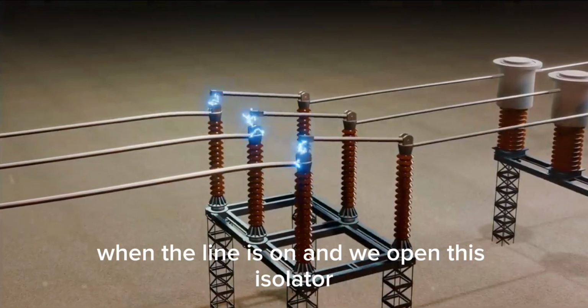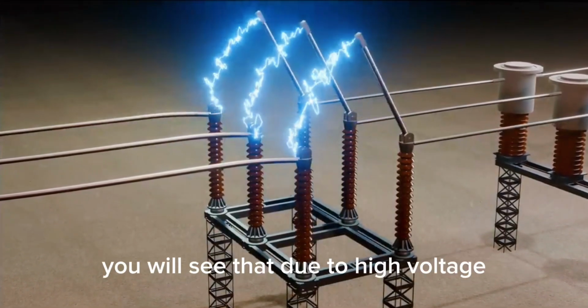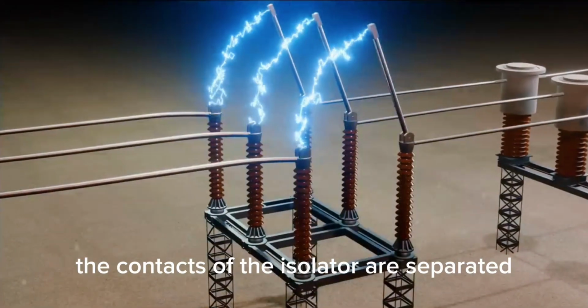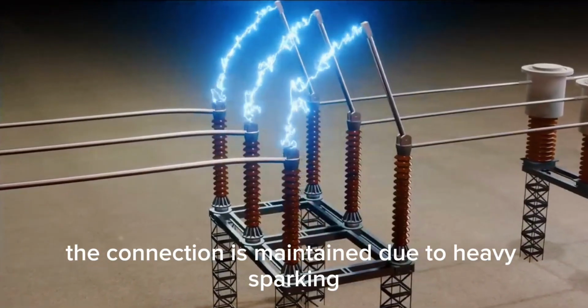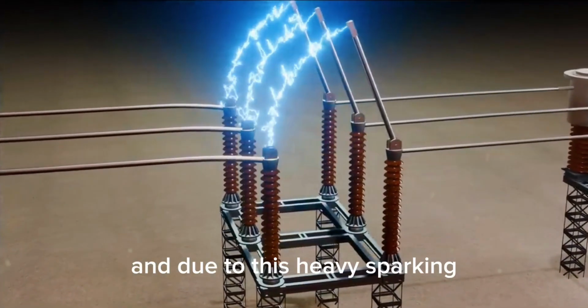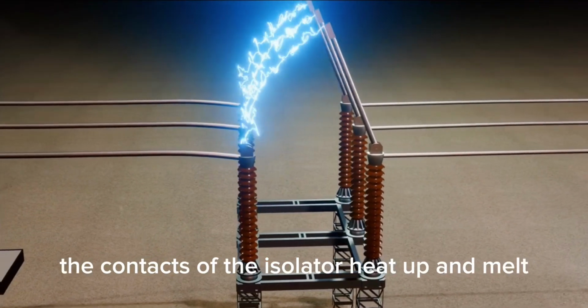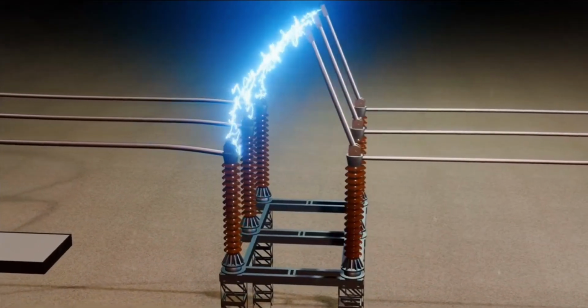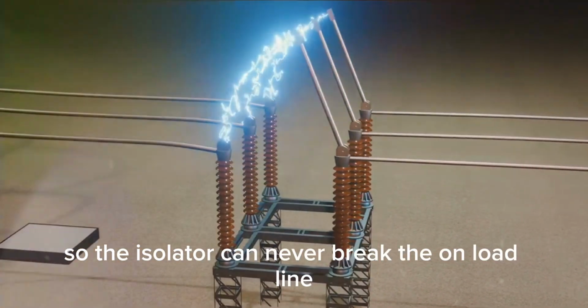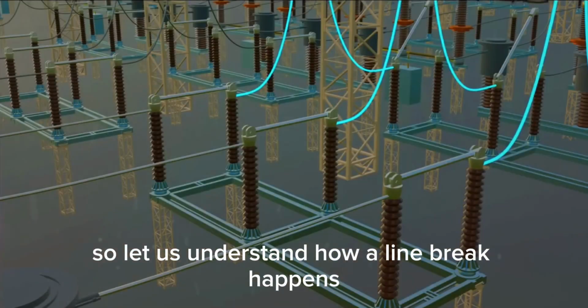When the line is on and we open this isolator, you will see that due to high voltage the contacts of the isolator are separated, but still the connection is maintained due to heavy sparking, and due to this heavy sparking the contacts of the isolator heat up and melt. So the isolator can never break the on-load line. So let us understand how a line break happens.